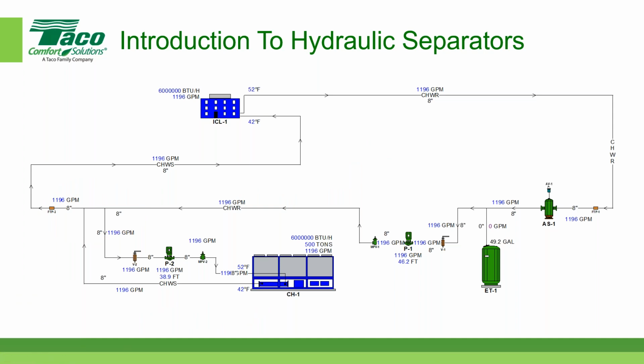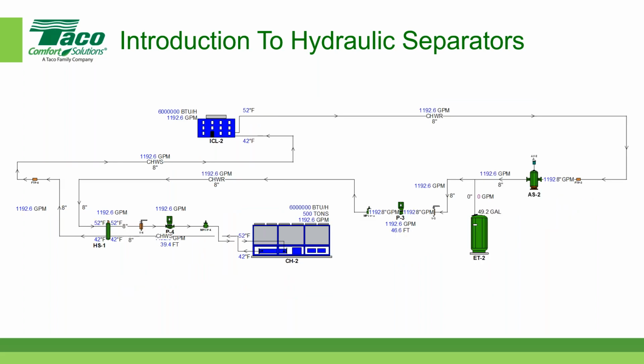Okay, now another thing we can do, this is sometimes referred to as a field designed hydraulic separator, but there's another option. The other option is that you can go with a prefabricated or pre-engineered hydraulic separator or bridge. And if we did that, it would look like this. So this little guy right here is a hydraulic separator. It's a pre-engineered device. There's the primary circuit on the right, the secondary circuit on the left. And instead of having just a pipe connecting the primary and the secondary circuit, we have this little guy here, which is called a hydraulic separator. And that's a pre-engineered device that Taco manufactures. We're going to get into what that looks like in a minute.